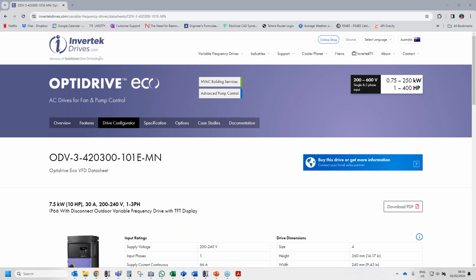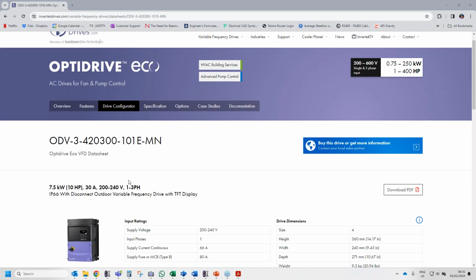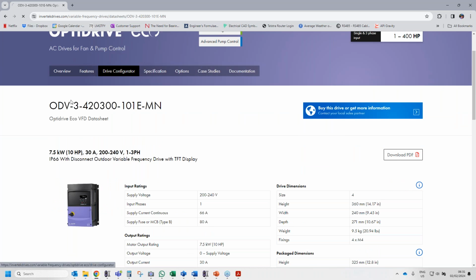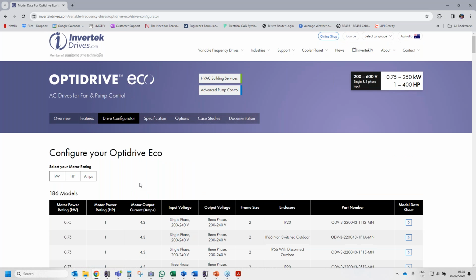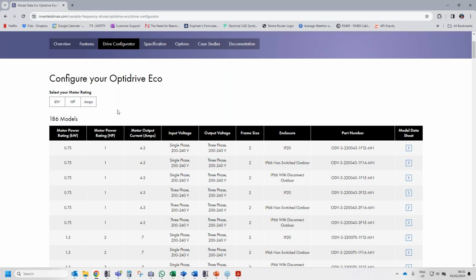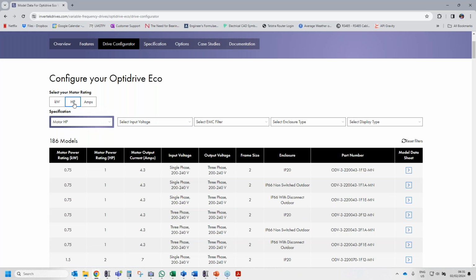So I see on the chat there, 15 horsepower is the biggest single phase in and 3-phase out unit that you'll need. With a single phase input and 3-phase output, the biggest that we do standard is 10 horsepower. Most VFD manufacturers, the biggest they'll do is about 3 horsepower. We go up to 10 horsepower with the Eco. But what we can also do, as I said, is derate it.